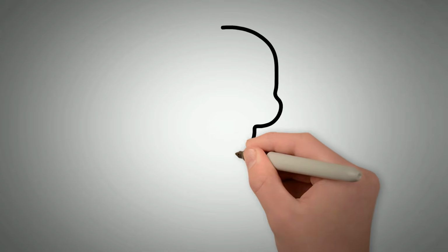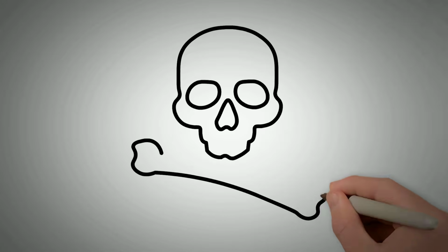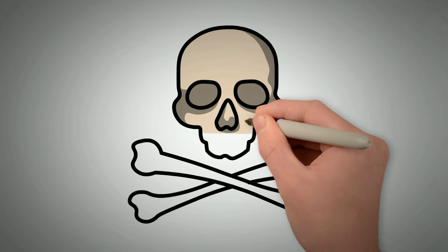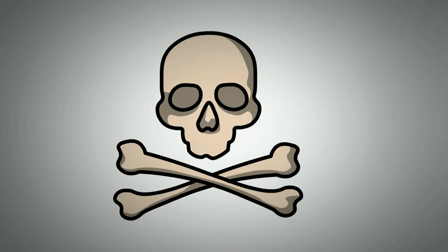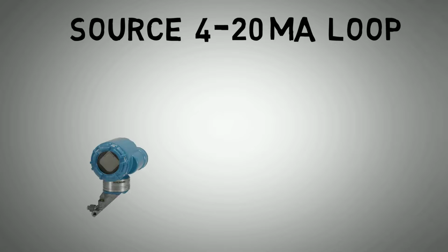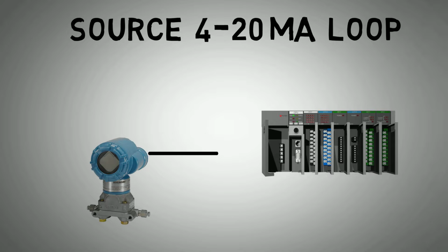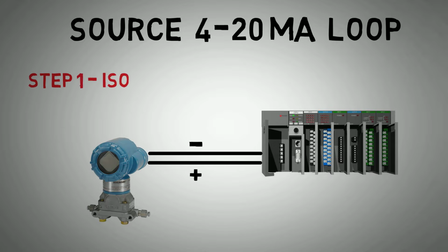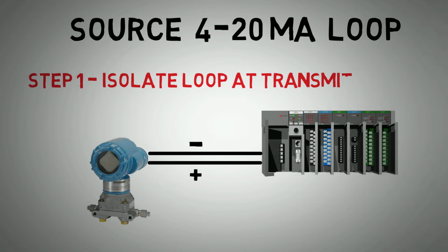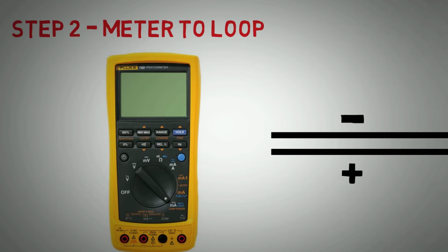Remember, electricity is dangerous, so only work on equipment you are competent to do so, and always check the voltages you are working with. For sourcing 4 to 20 milliamps on a loop that is powered from the transmitter, follow these steps. Step 1. Isolate your transmitter loop and disconnect your transmitter at the head. Step 2. Put the transmitter into milliamp loop mode.